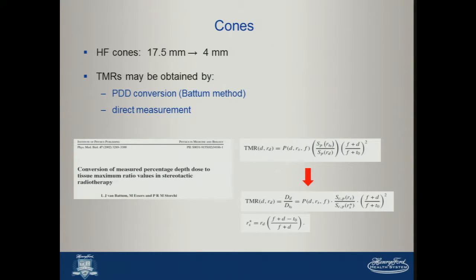Okay, cones. We have cones that range in size from 4 millimeter up to 17.5 millimeter. With cones, you're interested in obtaining the TMRs, and they can be obtained by two methods: the PDD conversion, so measure the PDDs and convert using the Battum method, or via direct measurement, in which case you're wrestling with your 3D scanning system to make sure it has the capability to raise and lower the water depth, etc. Just here I've included the Batum paper and the traditional TMR relationship for converting PDDs to TMR. Here it becomes a little bit more complex in that case. The Battum conversion method is a modeling method, so it has some inherent uncertainties in it.